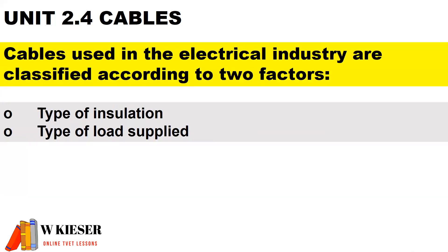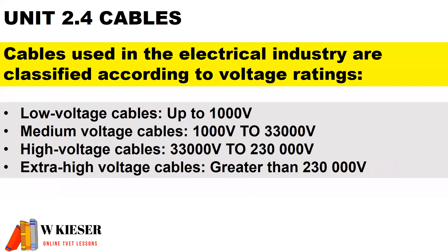Cables used in the electrical industry are classified according to two factors: the type of insulation, and the type of load supplied. They are also classified according to voltage ratings. Low voltage cables are up to 1,000 volts. Medium voltage cables are rated between 1,000 volts to 33,000 volts. High voltage cables are rated between 33,000 volts to 230,000 volts. Extra high voltage cables are greater than 230,000 volts.